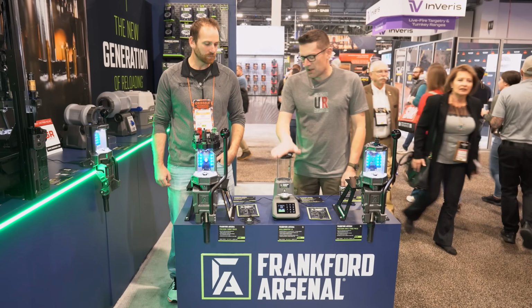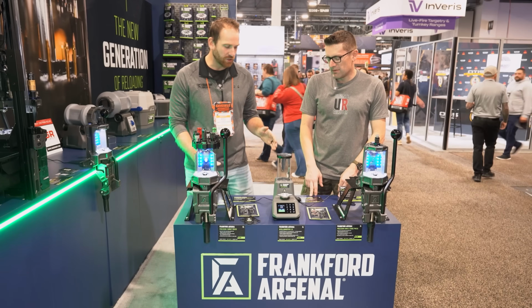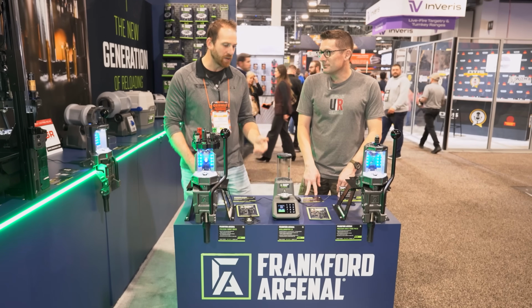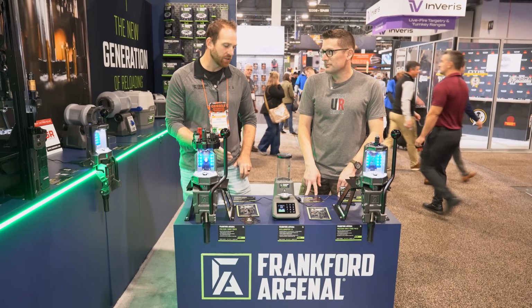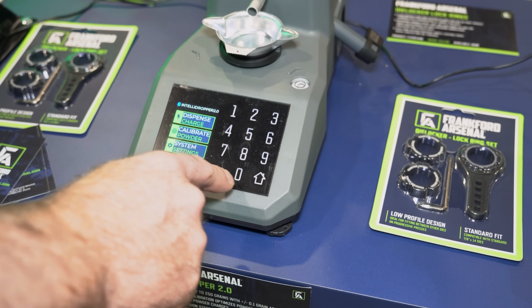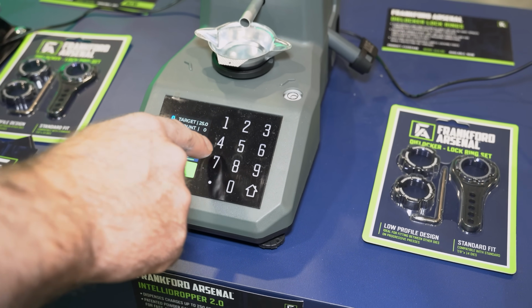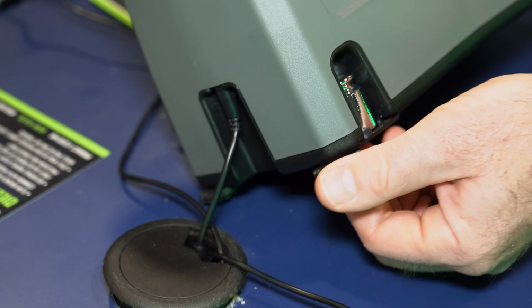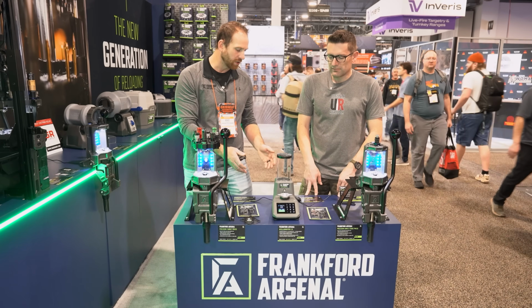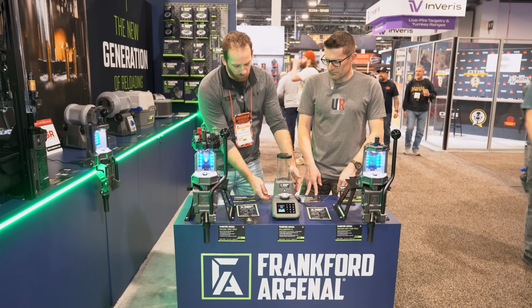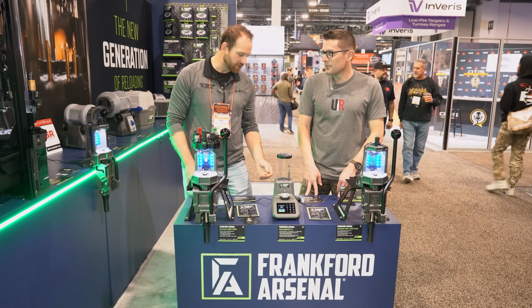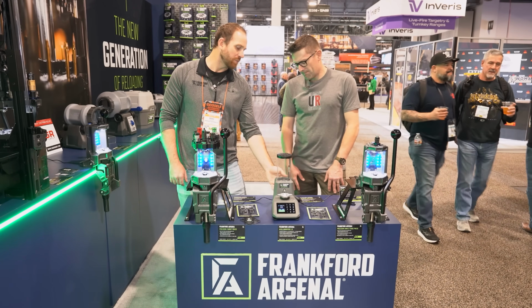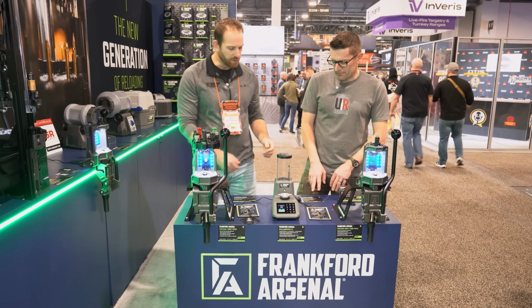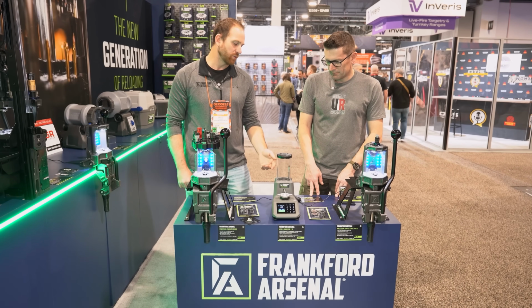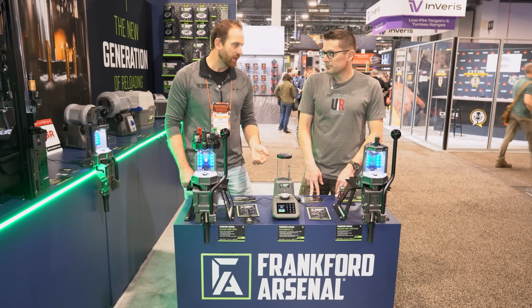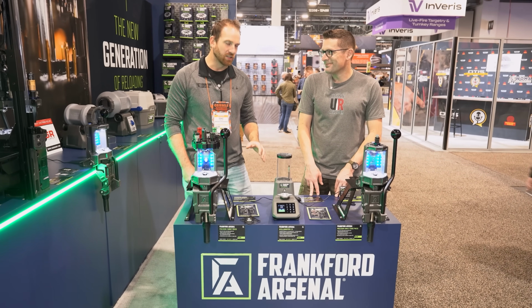All right, let's talk about Intellidropper 2.0. So this has all the same features as our original Intellidropper. It's still Bluetooth, it still has the powder calibration, but we've addressed a lot of the things that we thought there were room for improvement on, like the screen. The screen and the user interface is all new. The feet are easier to adjust. They protrude out past the edge of the unit a little bit, so they're easier to get a hold of. The calibration weights are stored on the inside, so it's not taking up space on your bench. This is a small thing, but the power cord now comes out the back instead of sticking out the side. That's great. The biggest change is going to be the old DC gear motor has been replaced with a stepper motor. So it's much more powerful, it's much more precise, and it's a lot quieter.